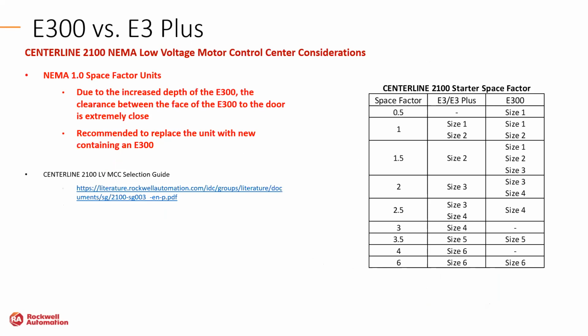An important thing to note when you're dealing with an E3 Plus in a motor control center, the NEMA 1 space factor buckets: due to the increase of depth, the clearance between the face of the E300 to the door is too close. It's still recommended at this time to replace the bucket with a new bucket containing an E300 as opposed to trying to retrofit the bucket to fit an E300. There's a lot of rewiring that will be necessary, and it's more cost effective just to get a new bucket. We are still working on that to see if there's any sort of workaround, but as of now, it's still recommended to purchase a new unit.